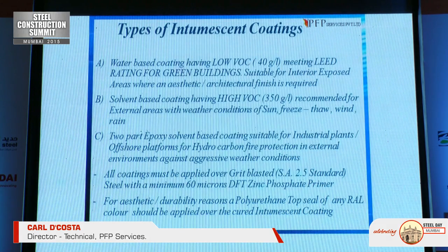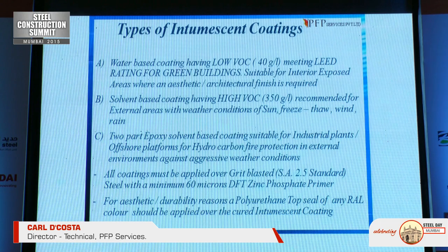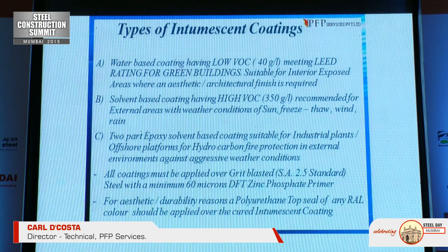The types of intumescent coatings: water-based coatings have a low volatile organic content, meeting LEED ratings for green buildings, and are suitable for interior exposed areas where an aesthetic architectural finish is required. Solvent-based coatings have a reasonably high VOC and are recommended for external areas where weather conditions — sun, freeze-thaw, wind, and rain — are prevalent. There is also a two-part epoxy solvent-based coating suitable for industrial plants and offshore platforms for hydrocarbon fire protection in external environments against aggressive weather conditions. All coatings must be applied over grit-blasted steel with a minimum of 60 microns dry film thickness zinc-phosphate two-part epoxy primer.